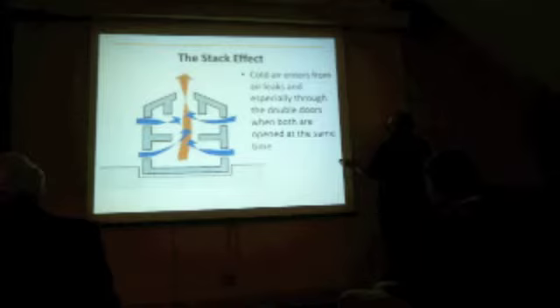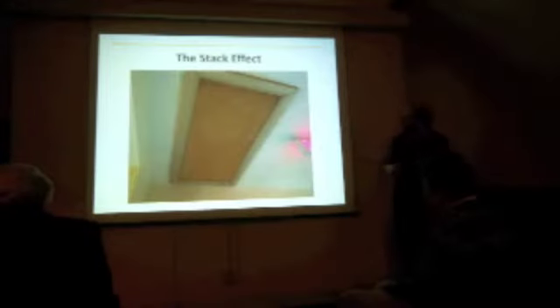called the stack effect. Any leak that you have at the bottom of your building is drawing in cold air. The cold air then is heated and rises. And if you have air leaks at the top, you've created essentially a chimney, and you're bringing cold air in at the bottom, it's heated up, and then you blow it out the top of the building. So any penetration that's near the top of your building is really important to air seal.